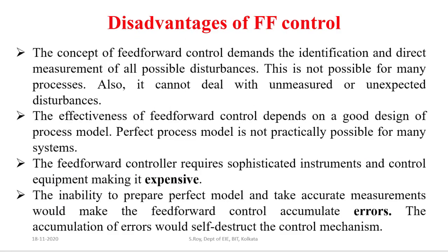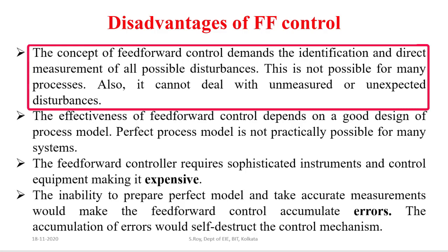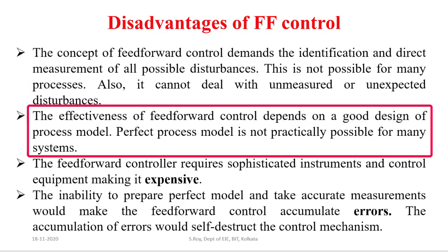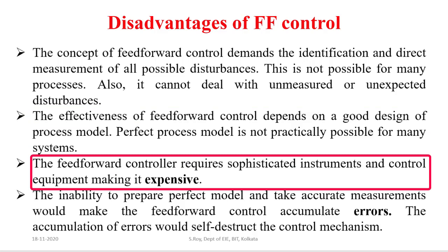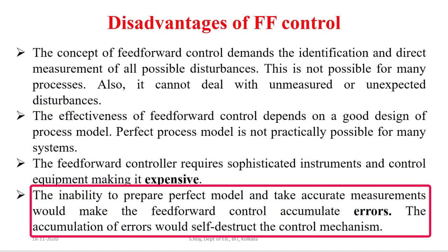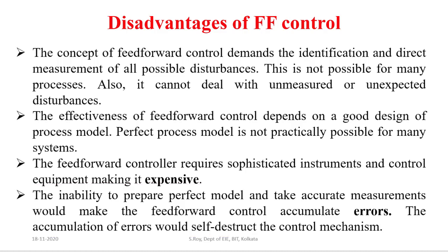The disadvantages of feedforward control include the requirement that all disturbances must be measured perfectly, which is not always possible in practice. A perfect mathematical model matched to process characteristics is essential — an inaccurate model creates negative effects on the control system. Feedforward control also requires extra equipment and instruments, making it more expensive. Inaccurate measurement of load variables or poor mathematical model design will cause errors in the system.